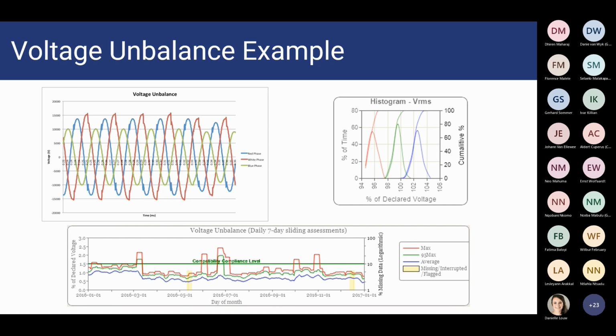And if we look at the 7-day sliding value, the scale is not that nice on this graph, but we can see the 2% limit, and your 95th percentile value, which is the green graph, is cut off here, but it is well above that 2% level for the period we're looking at. And here's just a longer assessment over time. You can see there are periods where your voltage unbalance values were higher than other times. Specifically here in the middle, your green graph, which is the 95% voltage unbalance value, is above your 2% limit.